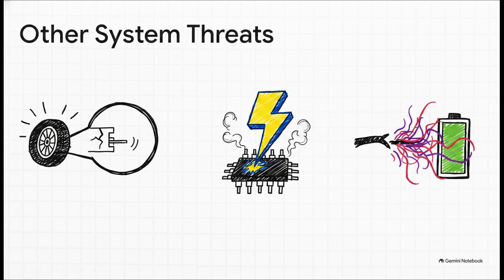Then we've got electrical threats, like a sudden high-voltage surge during maintenance that can instantly fry the multiplexer chips. And finally, crosstalk: when a wire breaks, the disconnected channel might drift to 0 volts, or totally max out to a fake 5 volts, which completely throws off the readings of the perfectly healthy adjacent cells.